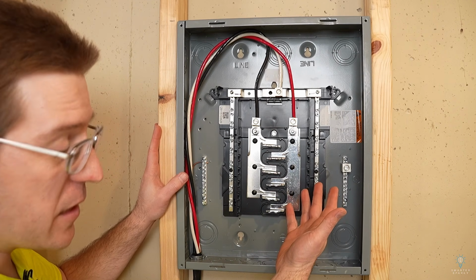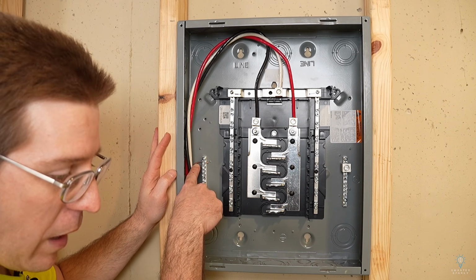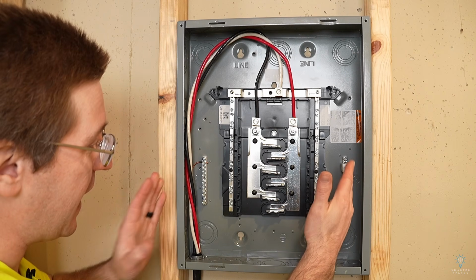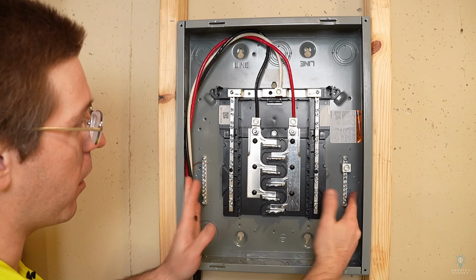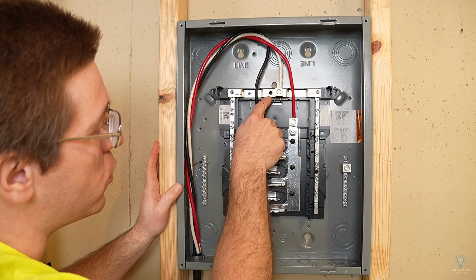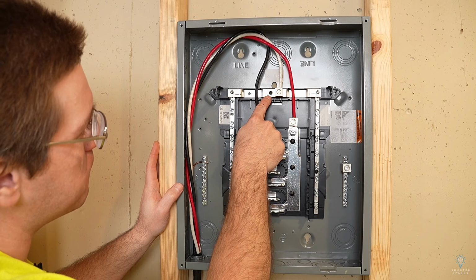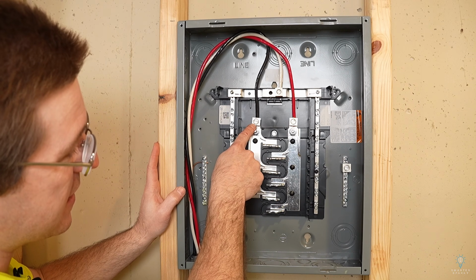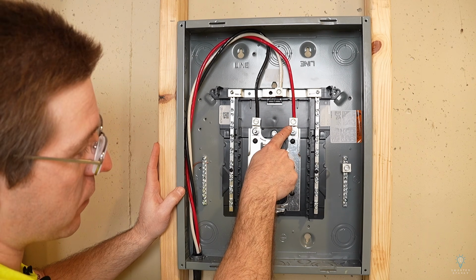And that's all there is to landing the feeder on the sub panel side. Again, our ground goes directly to the ground bar, and it has to stay directly on the ground bar. And our neutral is completely separate, and we do not install that green bonding screw. Our line 1 comes directly to this lug, and our line 2 comes directly to this lug.